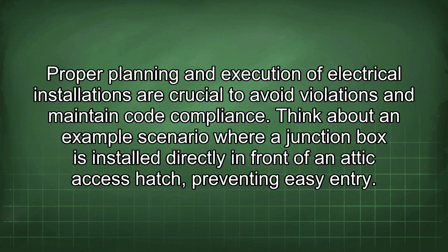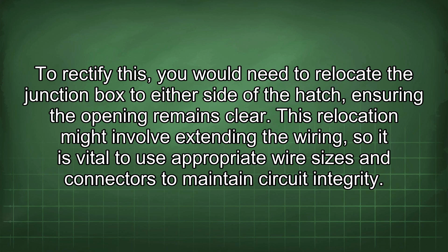Think about an example scenario where a junction box is installed directly in front of an attic access hatch, preventing easy entry. To rectify this, you would need to relocate the junction box to either side of the hatch, ensuring the opening remains clear. This relocation might involve extending the wiring, so it is vital to use appropriate wire sizes and connectors to maintain circuit integrity.